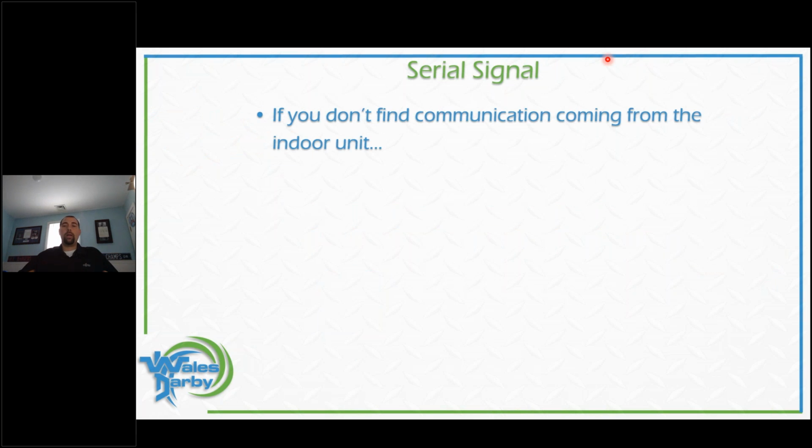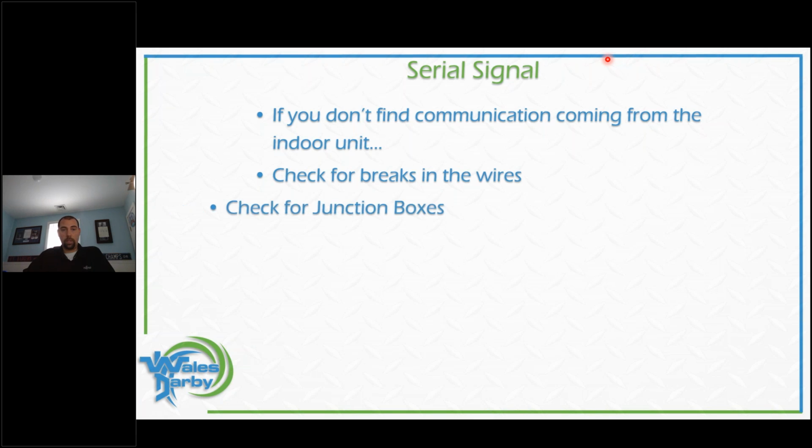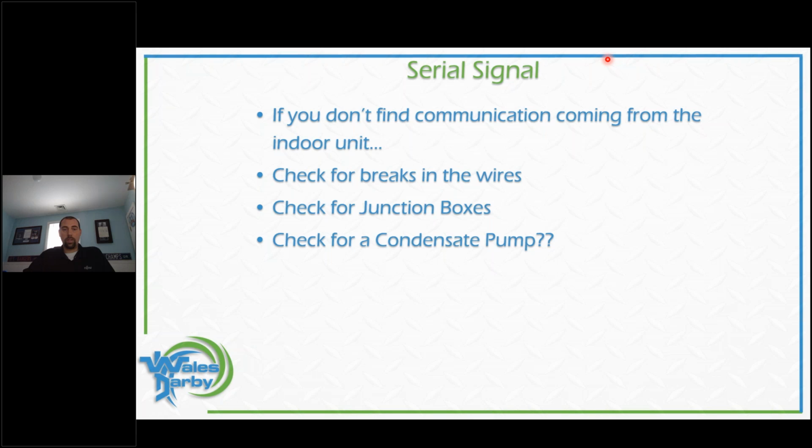So if you don't find communication coming from the indoor unit, right? If the outdoor is doing good, we got some communication there, but it's not coming from the indoor. So we got to make sure definitely those wires are good, like we just said. Make sure there's no boxes and stuff like that, but also check for a condensate pump.